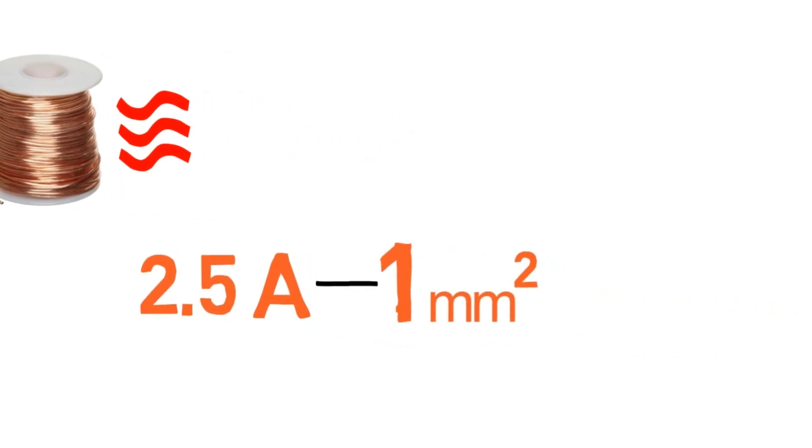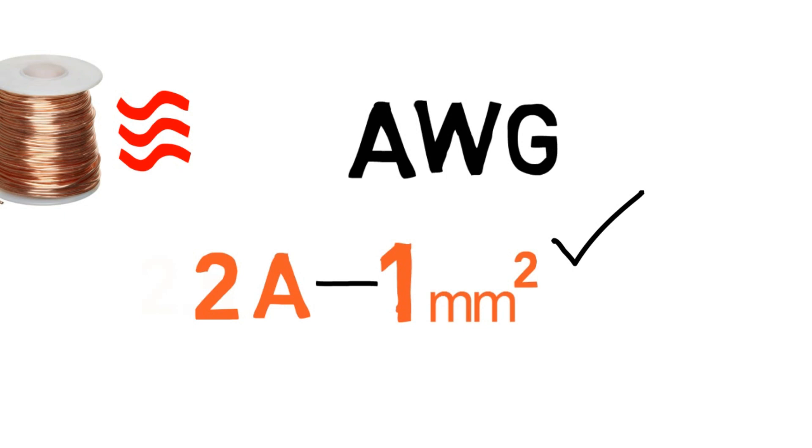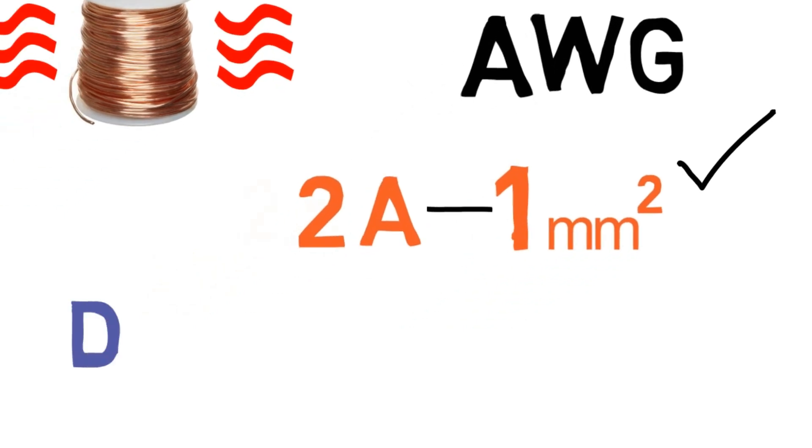According to our design, 2 amps is the load current. The wire having 1 mm square cross-sectional area will be sufficient for us. For more details you can see the American Wire Gauge chart for reference. This wire will have the diameter of 1.12 mm.